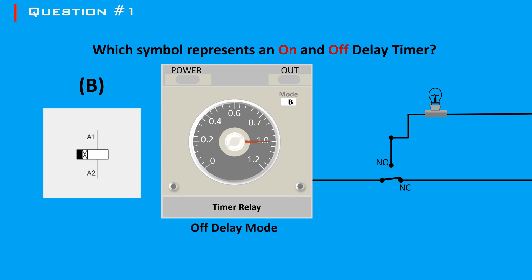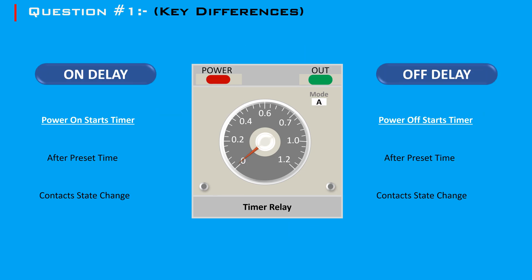In off-delay mode, when the input signal is applied, the output contacts change state immediately. The timer starts counting the preset delay time only when the input signal is removed — for example, 1 minute. After the delay time elapses, the output contacts return to their original state. It is typically used in applications where a delay is required before turning off a device or circuit, such as delayed deactivating of alarms or signals, or timed lighting control.